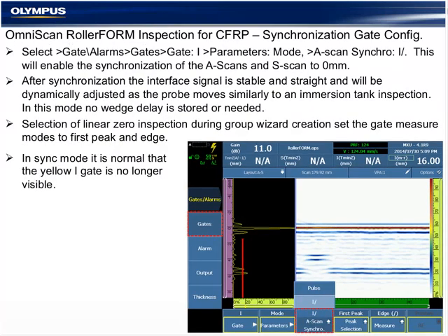The normal mode for this would be pulse. And again, our signals, both for gate A for the detection readings and for gate I for the synchronization readings, are going to be using the first peak that crosses the gate and the edge of that peak. And these functions for the A-scan gates are also included in the readings that are associated with them.